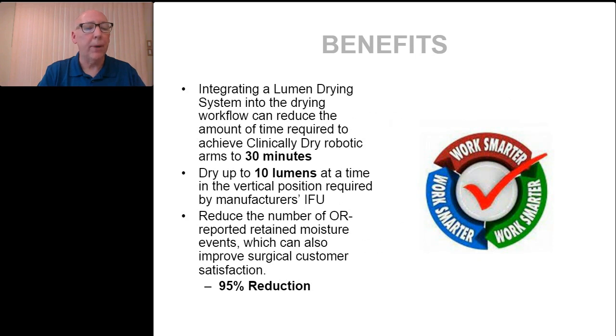And again, there's a lot of benefits to having those devices be in fact dry. It can also save a lot of time, and in this case, save as much as an hour less of drying time per cycle. This time savings can reduce processing time for these devices overall by as much as 40%. In addition, the devices are positioned properly and secured in the system itself, protecting them from potential damage. So the novel lumen drying system positioned in a drying cabinet orients the arms properly. They're in the cabinet, positioned properly, and protected from any potential damage.